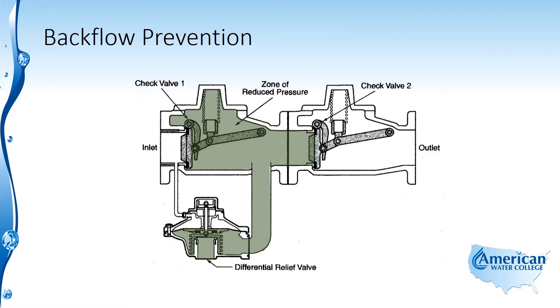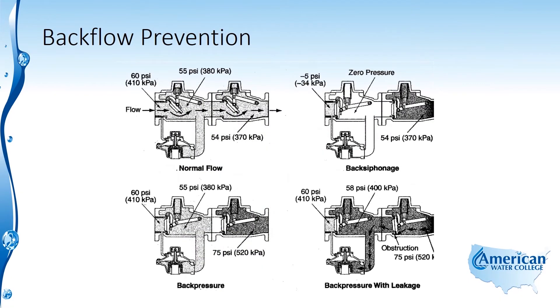Here we can see different configurations from normal flow to back siphonage, back pressure, or back pressure with leakage. In the upper left hand corner, under normal conditions, we have water flowing through this double check valve assembly and the relief valve is closed. We have an inlet pressure of 60 psi, a slight head loss through the valve to 55 psi, and 54 psi leaving the valve — a pressure drop of about 6 psi through the valve, which is normal.